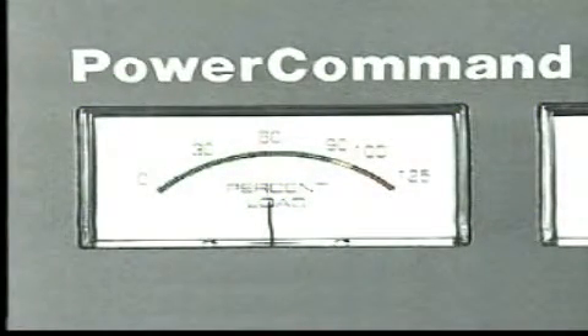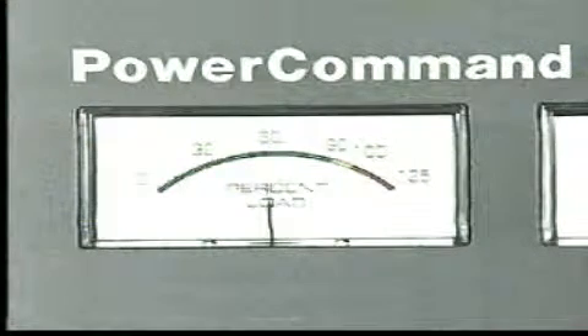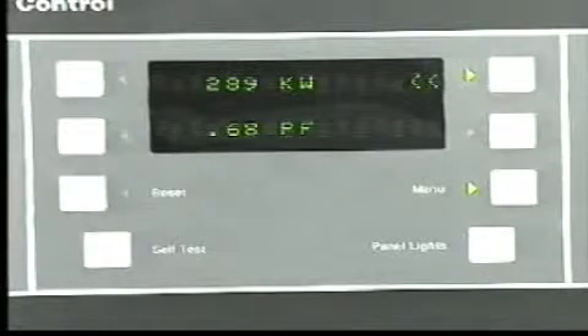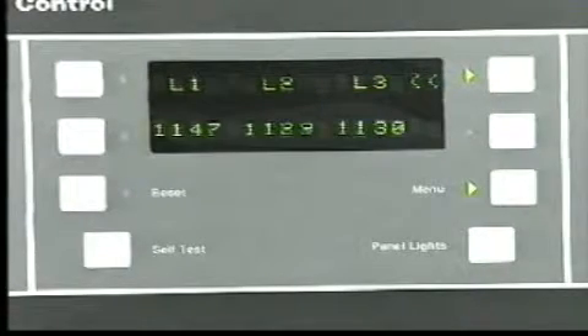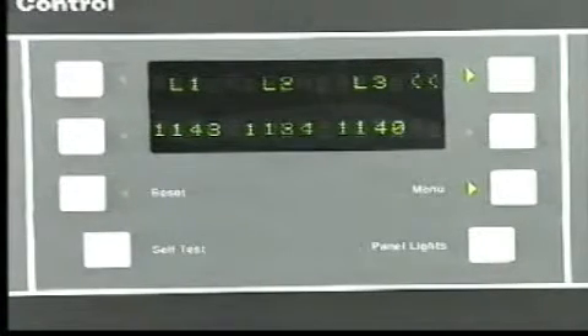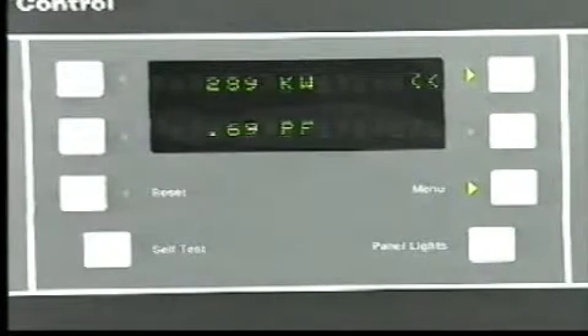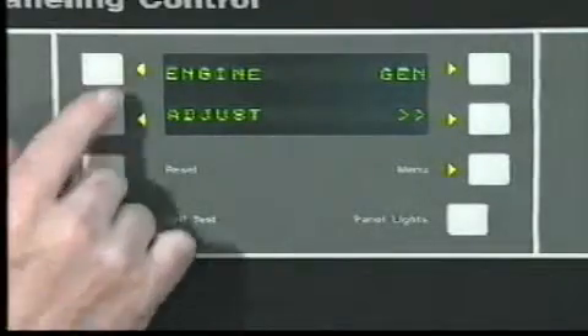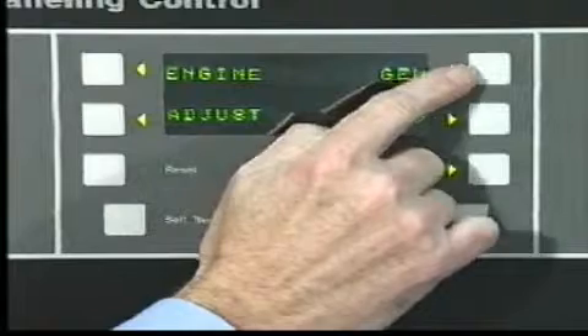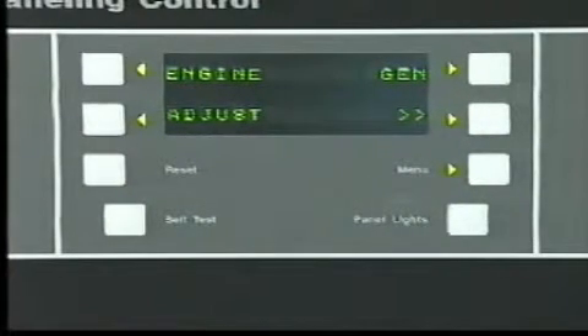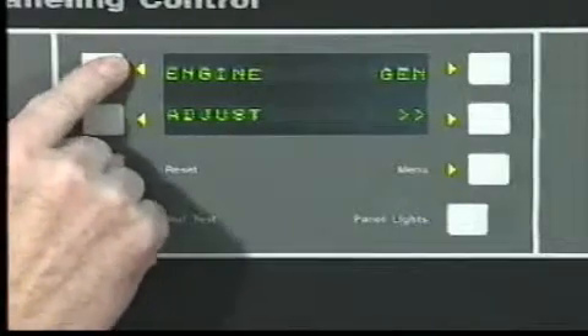Among the many standard features on the power command control, this kilowatt meter gives you a clear indication of total kilowatt output that an ammeter alone can't do. The same information given by the kilowatt, frequency, volt, and amp analog meters can also be provided by the digital display. The digital display also shows power factor and kilowatt hours. Like all good computer software products, the digital display enables you to follow the menu path without referring to a manual. The 4 tactile switches here help you access operating information and allow you to make adjustments within the menu-based system. When you press the switch, you can feel it engage.